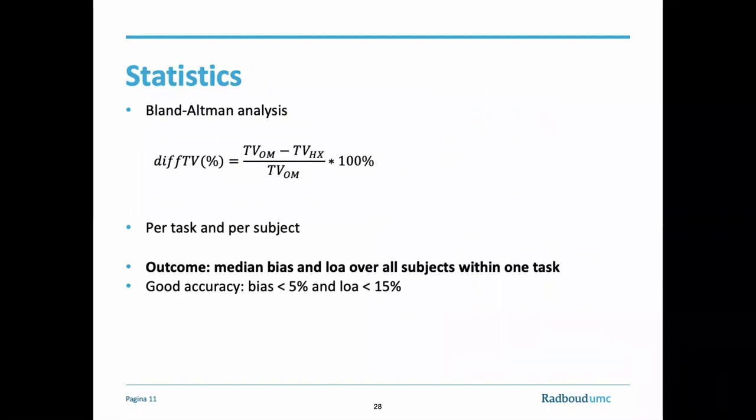Bland-Altman analysis was used to determine the agreement between tidal volume measured with the Hexoskin and the Oxycon mobile. The difference, diff-TV, between both methods was represented as a percentage of tv-om, the Oxycon mobile. Per task and in each individual, a bias and limits of agreement were derived, and the mean or median bias and limits of agreement over all subjects was taken per task. A priori, we determined the bias had to be below 5% and the limits of agreement had to be within 15% to have a good agreement between both methods.